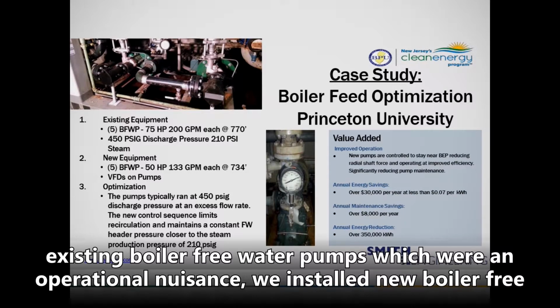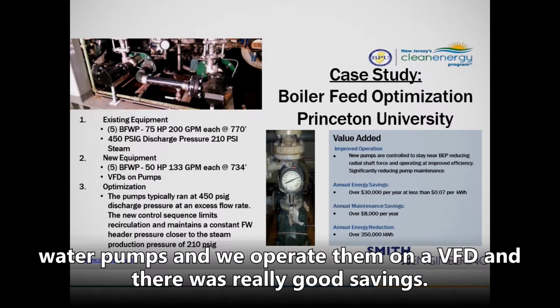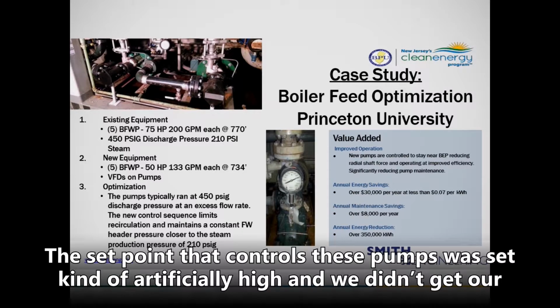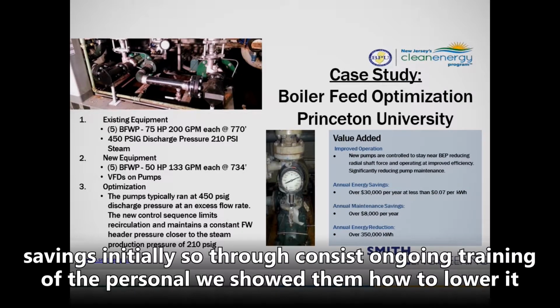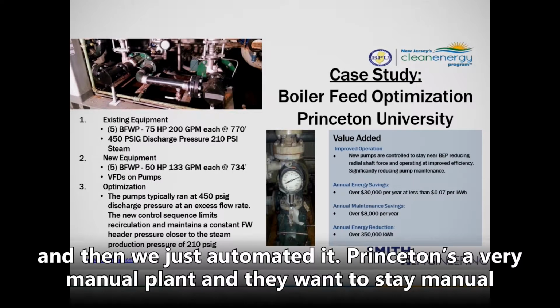But what we did for this project is we replaced the existing boiler feed water pumps, which were an operational nuisance. We installed new boiler feed water pumps, and we operate them on a VFD. And there was really good savings. The set point that controls these pumps was set kind of artificially high, and we didn't get our savings initially. So through consistent ongoing training of the personnel, we showed them how to lower it, and then we just automated.